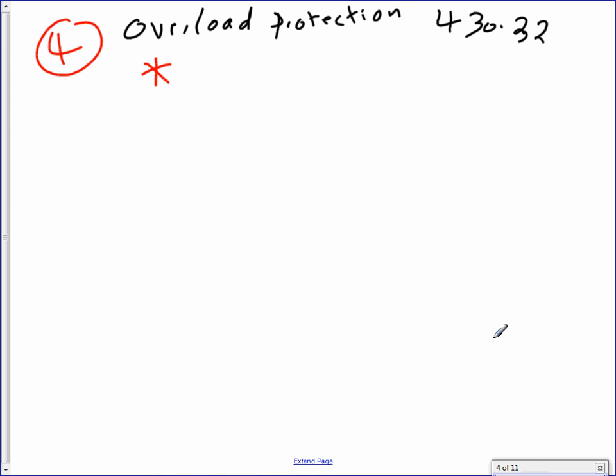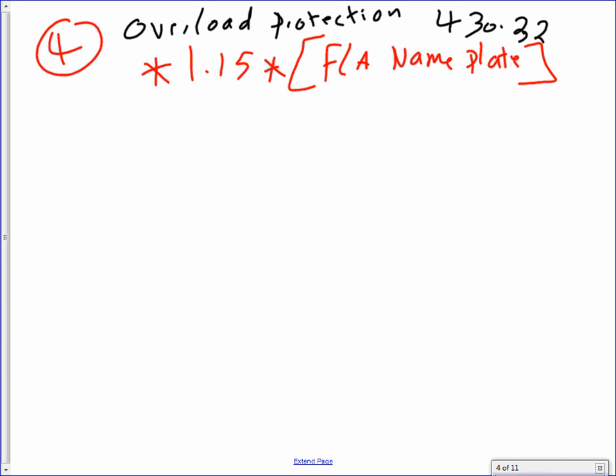Okay, so we go there. Now, this is how it goes. Then you go 1.15 multiplied by, but from the code book, guys, you need the full load amps, and next to it, nameplate. From the nameplate, not the book that I provided for you. The nameplate. Did you guys hear me? What's a nameplate? You go to the motor itself and you read it. It says the current is this amount. The nameplate. So it's not the 17.